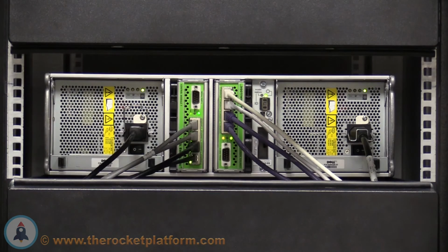In the rear of the machine you will see the control modules. If the faulty control module is in the secondary state now, it will have a green light for the PWR and an amber light for the ACT. If the control module is in the not installed state, the controller will have a green light for the PWR and a red light for the ERR.